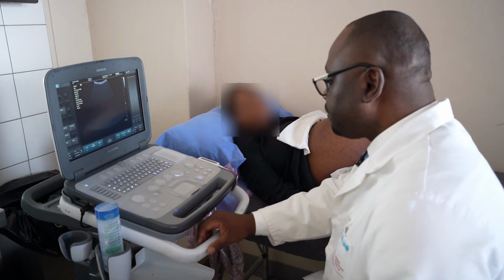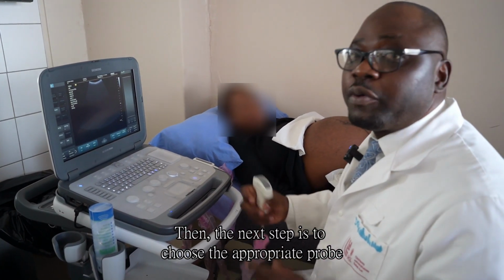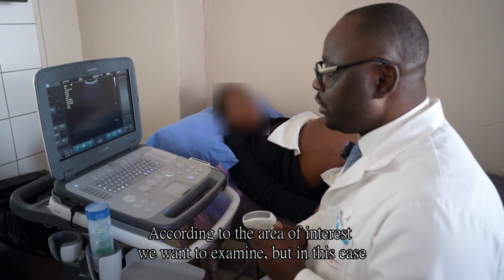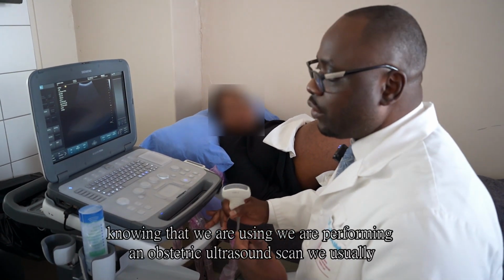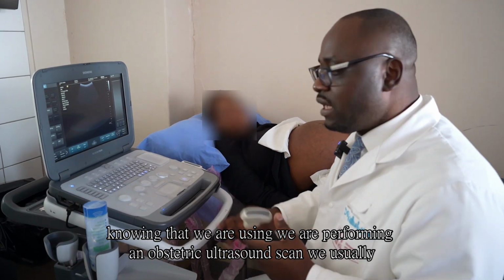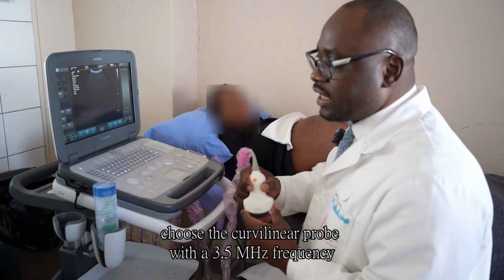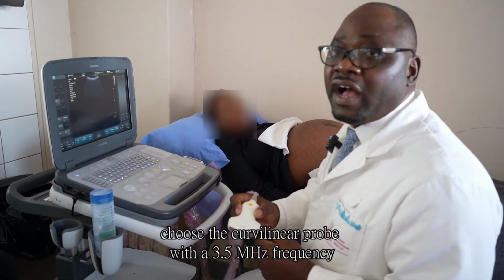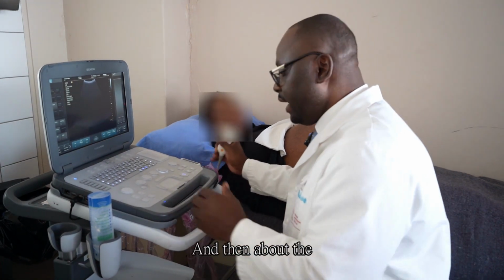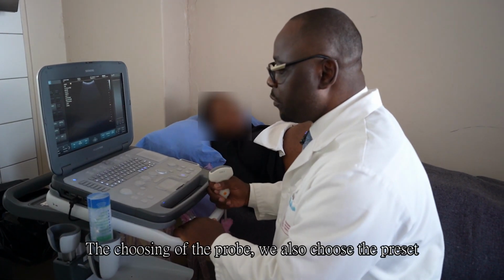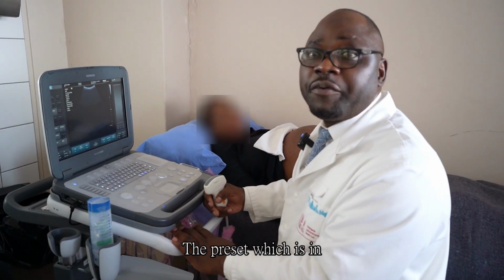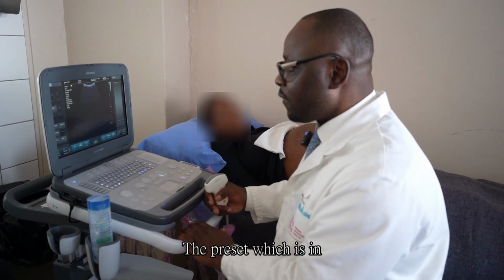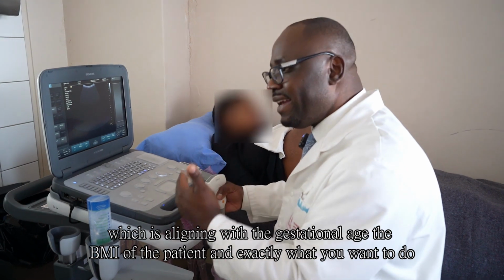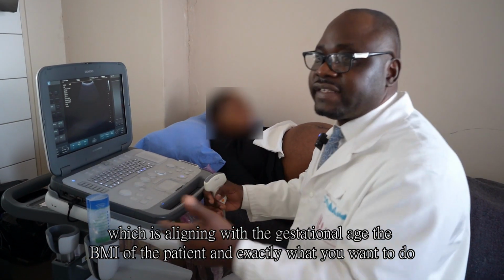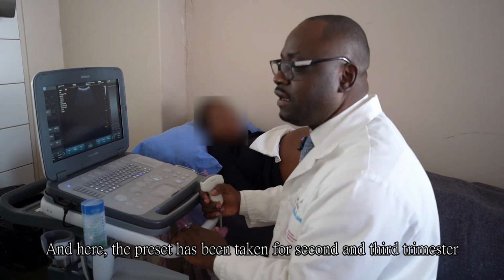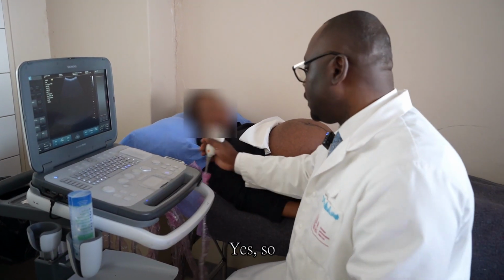And after doing that, the next step is to choose the appropriate probe according to the area of interest we want to examine. But in this case, knowing that we are performing an obstetric ultrasound scan, we usually choose the curvilinear probe with a 3.5 megahertz frequency. And then apart from choosing the probe, we also choose the preset, which is aligning with the gestational age, the BMI of the patient, and exactly what we want to do. And here, the preset has been taken for second and third trimester.